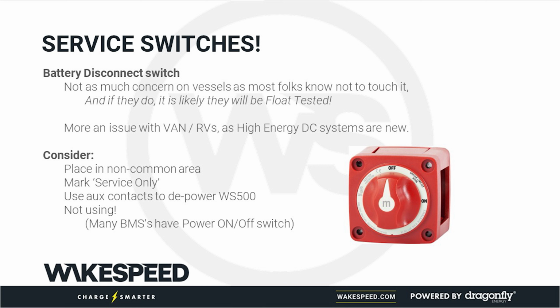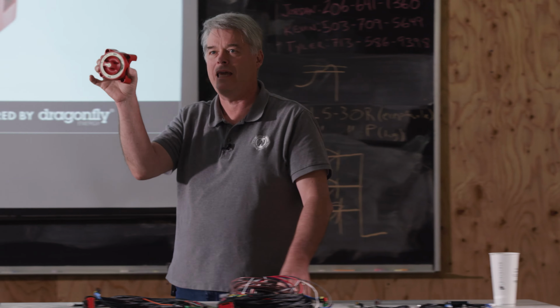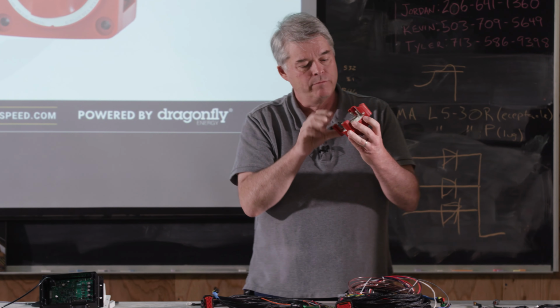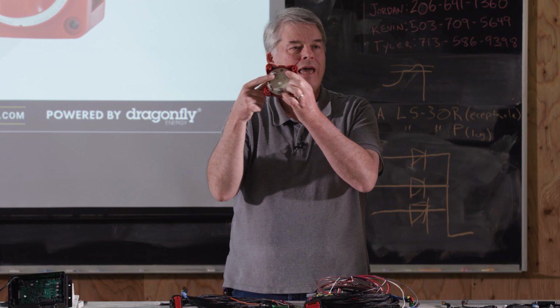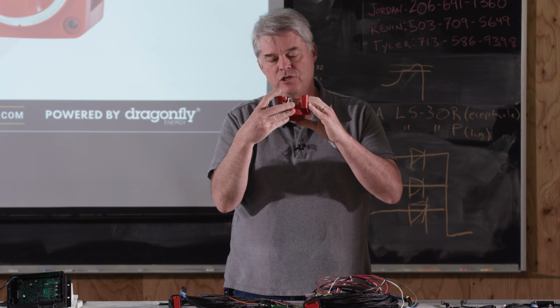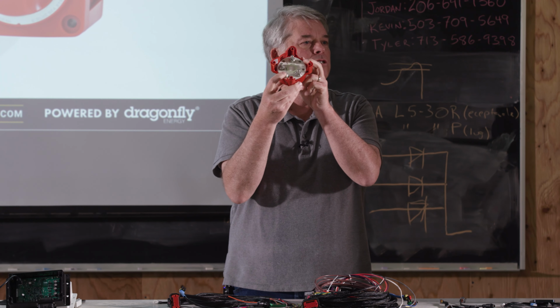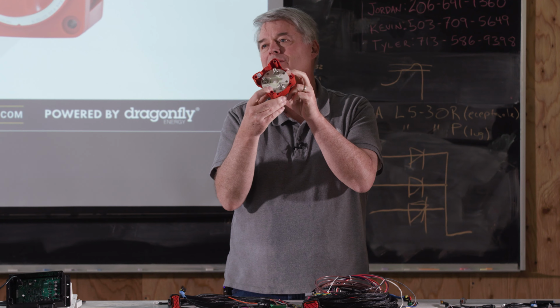Service switches. We talked about this, and you've got an example of one over there. Is this the one with the aux contacts or not? Okay, perfect. So you can get these. This is actually an AB switch, a rather complex one. But if you look on the back, you'll see there's the heavy power terminals, and then you see these little ones here. These are the field disconnect. You'll see them called field disconnect.